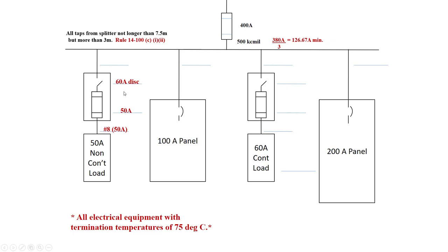This has no real bearing on the size of this tap conductor. When it was less than three meters, we had to size this wire based off the fusible disconnect ampacity. If we did that, that would give us number sixes, good to 65 amp, but that is not one-third the ampacity of the 500 KC mil. We have to bump this tap conductor up to a minimum capacity of 126.67 amps.